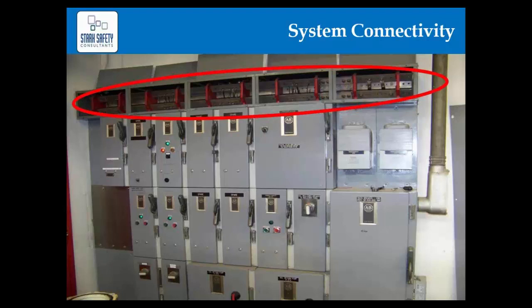So we definitely don't want to get too comfortable when we do that. Some big setups of gear, assembly, and components - here's one where we want to make sure we don't forget to check the overall connectivity. All these different buckets, the wires came in and out of this top busway connection up at the top, so we need to make sure we're mapping that out and not take for granted just opening up each cabinet. We need to open up this top and look at how all those wires are connected.